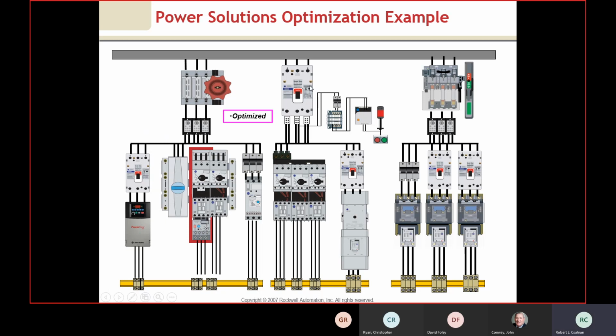If we look at the middle application, we'll see a molded case circuit breaker with multi-tap lugs. Notice we have the ability from here to tap off lower power. So we're going to probably pull 120 volts off of here to wire into an application, just doing the multi-tap. So we eliminate this space and the cost.